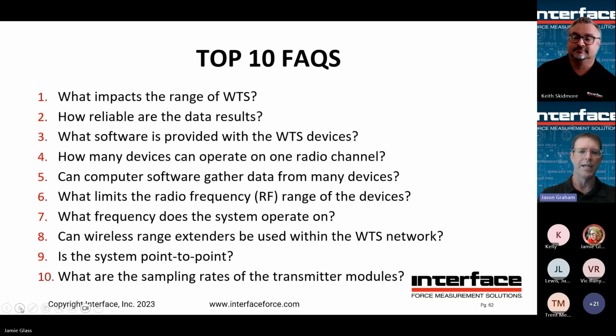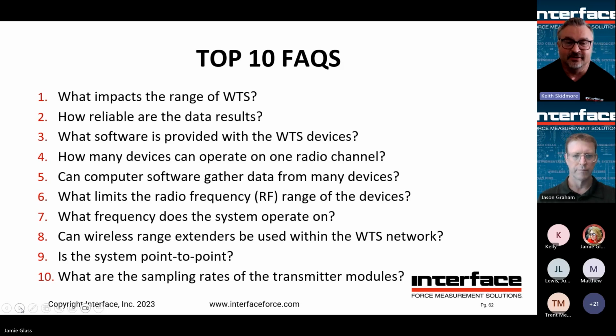What limits the radio frequency range of the devices? Well, the RF frequency itself is going to dictate the range to some extent. The higher you go in frequency, the shorter your range. Also, anything that could impede or block your RF signal. You think of anything else, Keith? Yeah, interference on the radio frequency too. It could be at a different channel, slightly different frequency, maybe better. And the toolkit does have spectrum analyzers. You look at the different channels. So say you're sitting next to a powerful router, you can look and see, oh, that's on channel 15. Well, don't use channel 15. You might want your WTS devices on channel 2, for example.